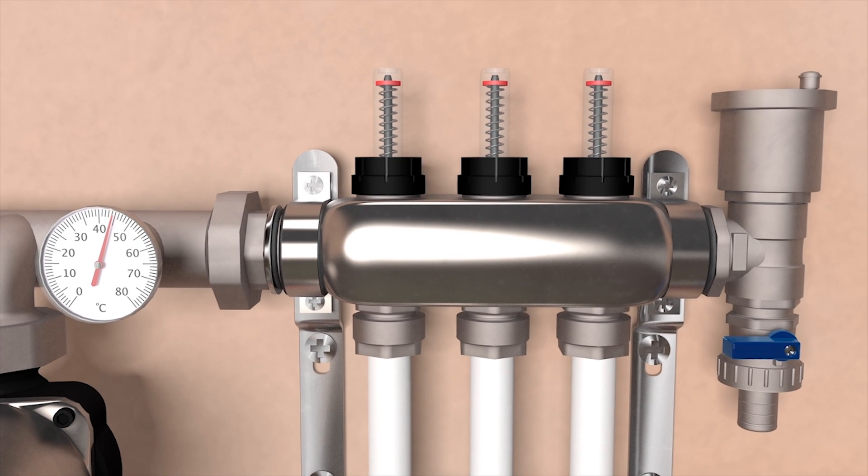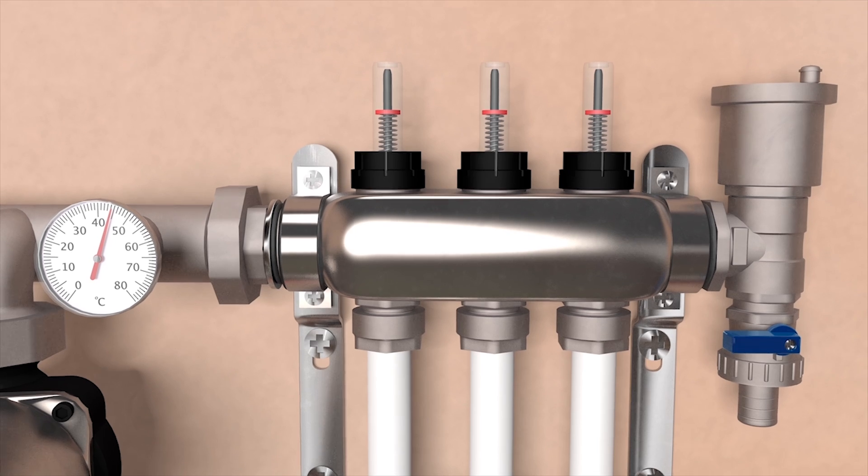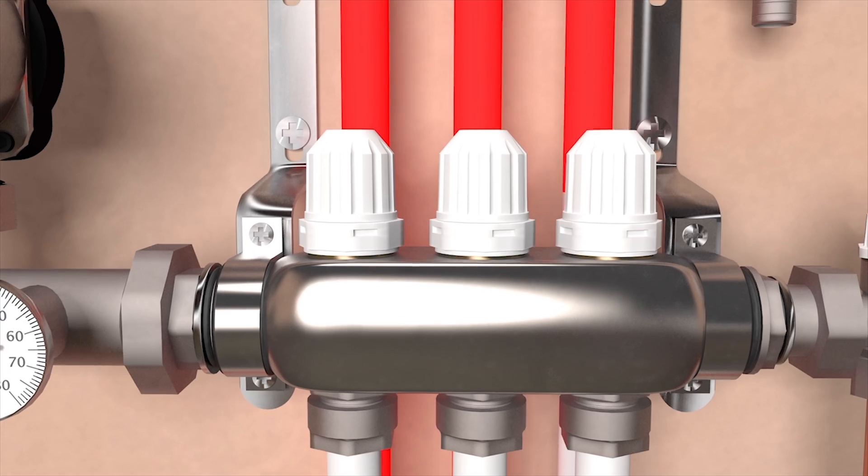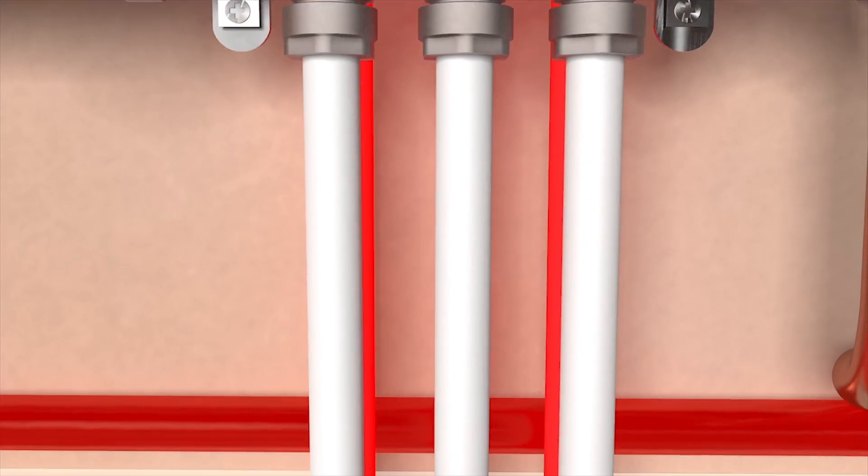Each pipe loop is regulated via a flow gauge. These flow gauges restrict or increase the flow of water going into each pipe loop. These are adjusted depending on the length of each individual pipe loop so that you have a balanced flow of water throughout your system.